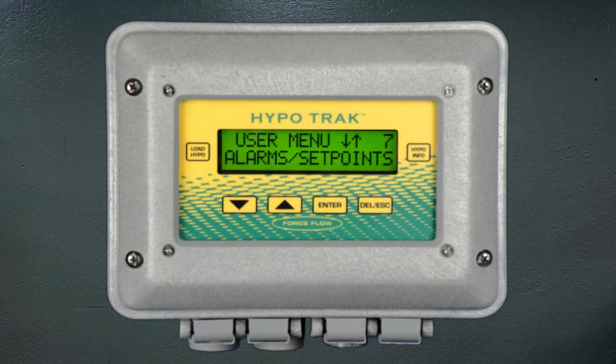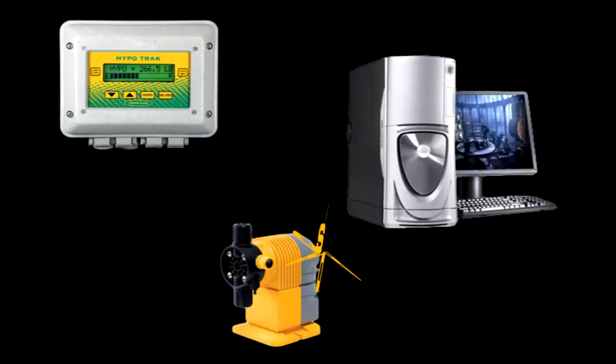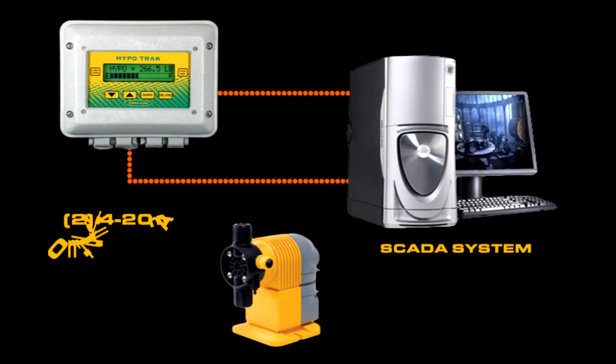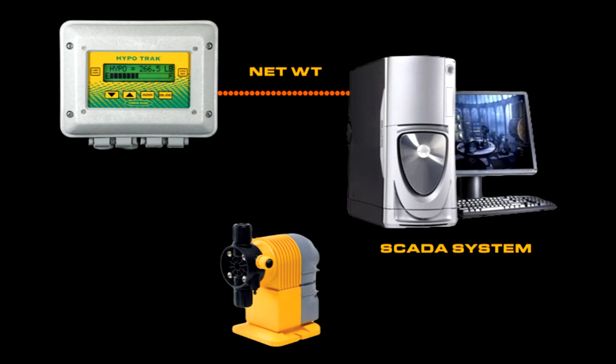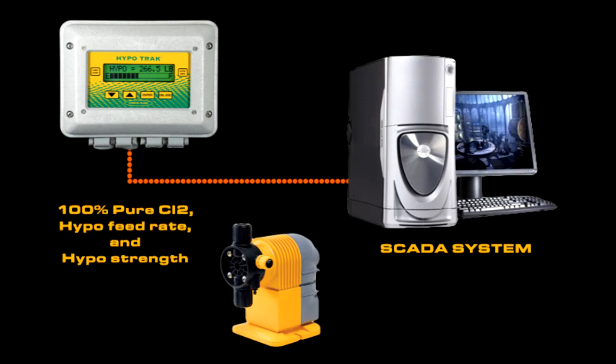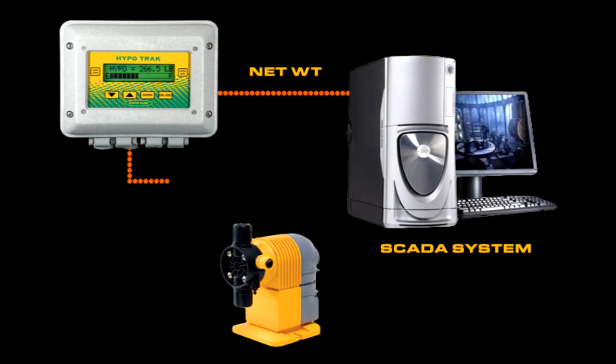Lastly, I'd like to discuss the type of alarms and output signals available to communicate with SCADA systems or metering pumps for automatic control. The HypoTrak has two 4 to 20 milliamp outputs available: one that outputs the net weight or gallons remaining in your tank, and a second that has the option of sending pounds of 100% pure chlorine remaining, current Hypo feed rate, or current Hypo strength. The second 4 to 20 output can also be connected directly to your metering pump to automatically speed up your pump as your Hypo gets weaker over time.